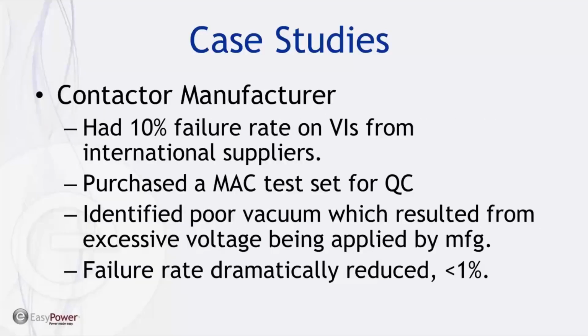Another case study was a contactor manufacturer who did not manufacture their own vacuum interrupters. They were buying these vacuum interrupters from an international supplier, and they were seeing a very high failure rate out of the box. In a lot of cases, they were able to catch them in their own QC testing, but many of them reached the field, and their customers were seeing failures on their contactors. So this was a very big deal to them.